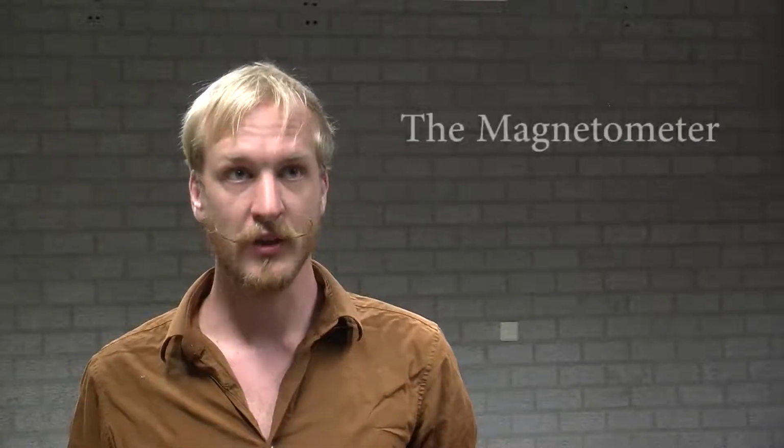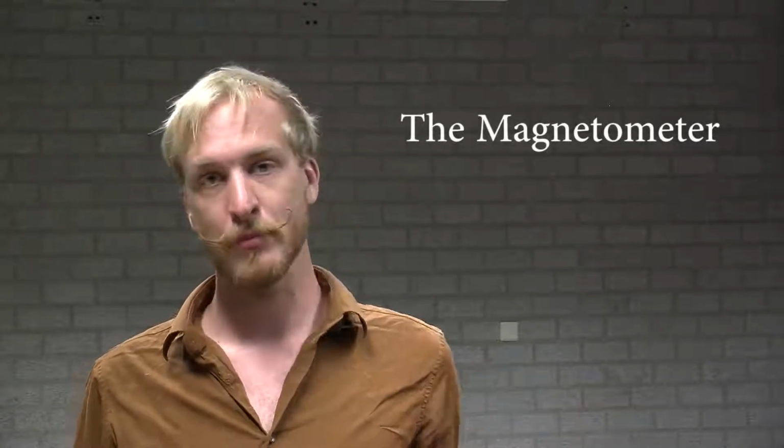However, because of the properties of the mu metal and the fact that we need holes in the room to pass through our cables, ambient noise will always be present. And because of this, MEG recordings also have to rely on smart sensor designs. To explain these smart sensor designs, let's start with the sensitivity of the most simple sensor, the magnetometer.